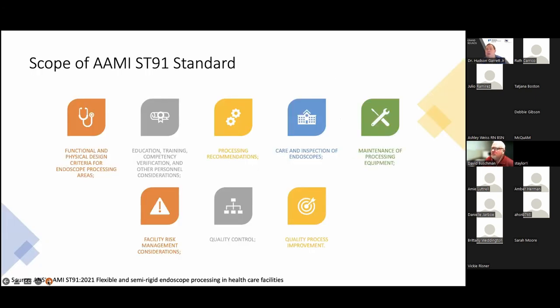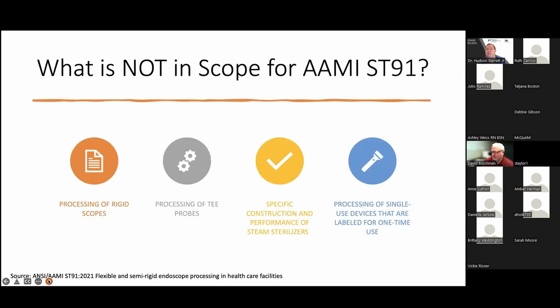Part of that standard breaks down a couple of important elements: how do we assess the device, how do we make sure it's properly maintained, what do we do from a quality control standpoint, are there ways we could design our reprocessing suites to be a little bit safer. All of these are important elements of any infection control program, and also reduce the risk of incidents with using some of these reusable medical devices.